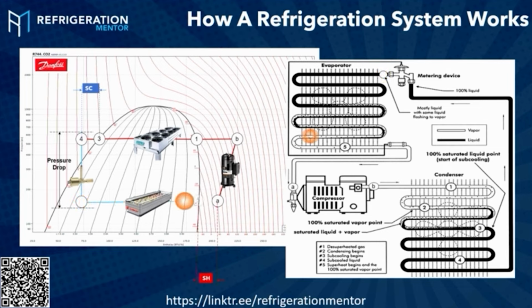It could be a case. It could be an A-coil. It could be even a plate heat exchanger. There are lots of different things it could be, but it doesn't matter. You just want to understand that as it starts to go through there and the fans are running across it, you got refrigerant boiling and bubbling. And as it's doing that, it's pulling heat out of the people. It's pulling heat out of the product. Okay? And then we leave from 5 to A, going back to the compressor.